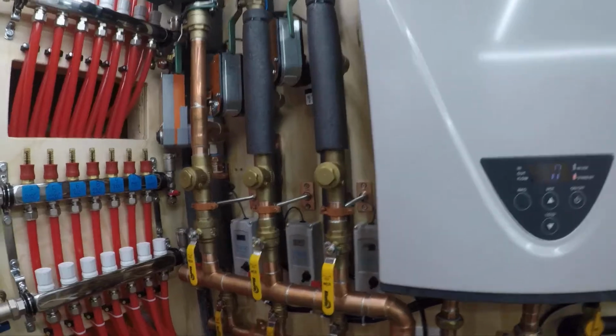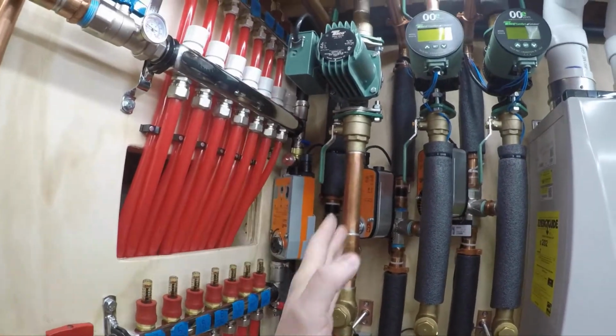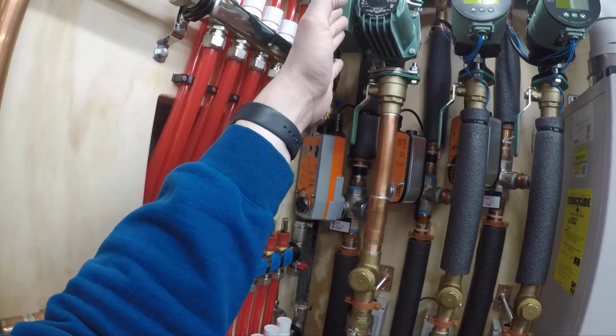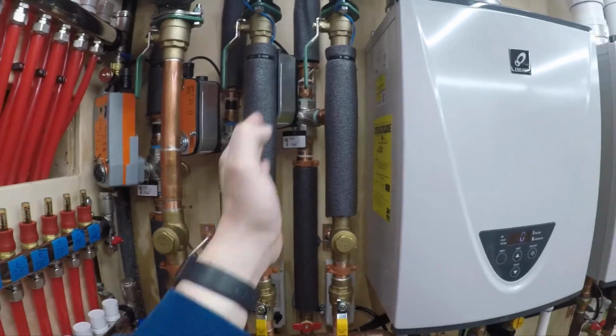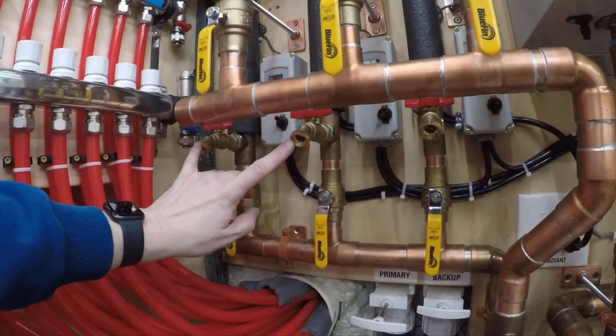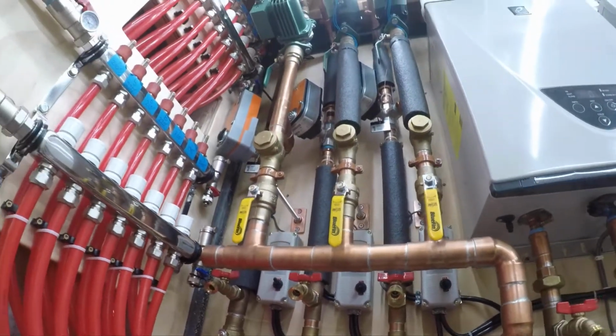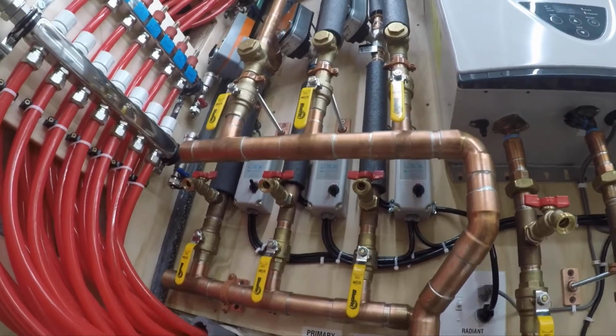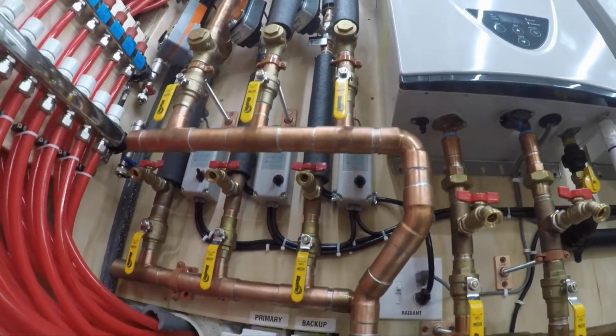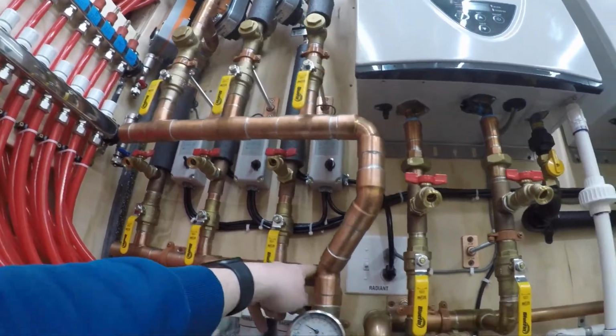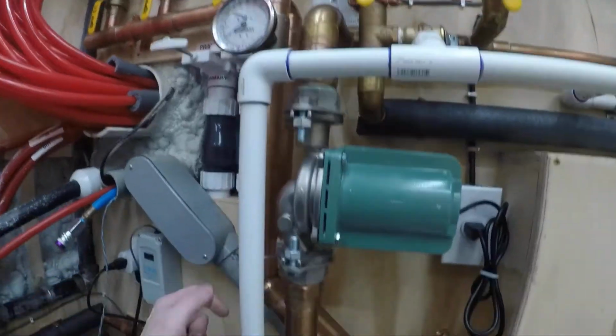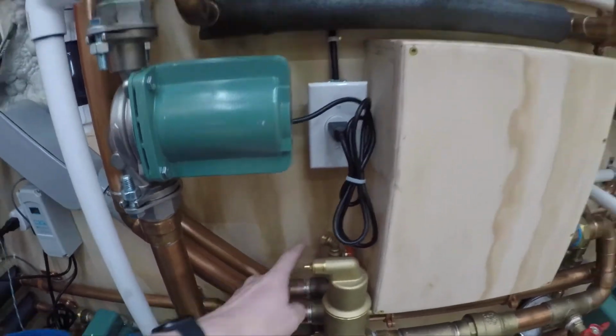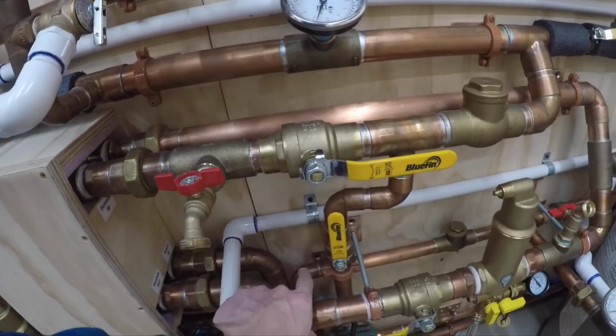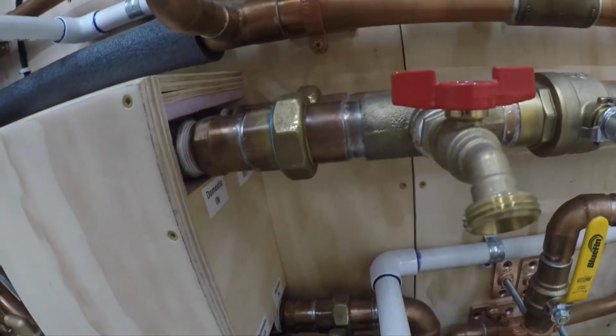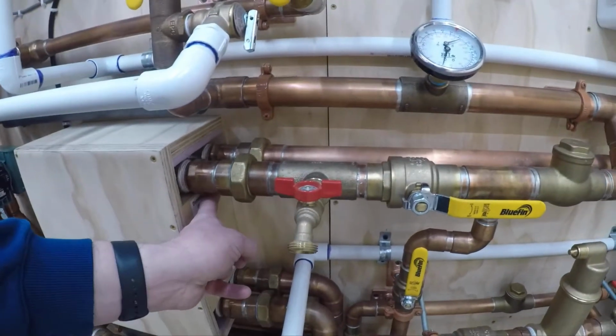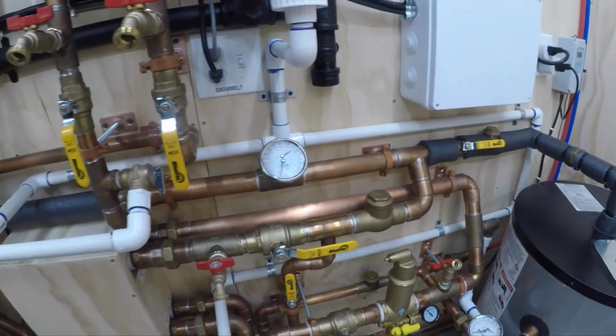So then, from the returns, when the zone is on and calling, the cool glycol comes down through the return of each zone into the return header. I do have purge valves here, and I did use these to purge. You can use them to purge the system, and it comes down back here through the 1.5 inch return. I have another fill and purge valve. Comes around the bottom there, does a 180, and comes into the input side or the cold side of the flat plate, picks up more heat, and goes out and starts the same loop all over again.